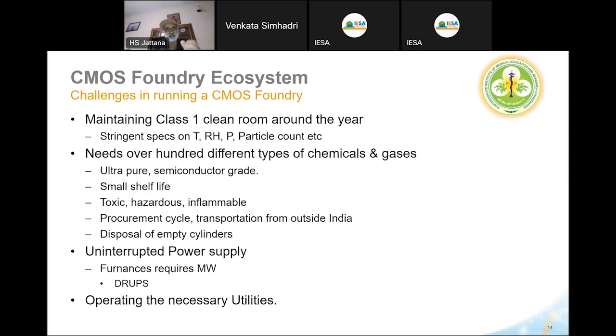DRUPS means there's an AC generator and an AC motor always running, with a big flywheel. Once AC supply is cut, the flywheel has enough energy to rotate the generator and supply power for close to a minute. In that time, the diesel generator comes on to supply power to furnaces which require huge amounts of power. These are tough requirements for these utilities.